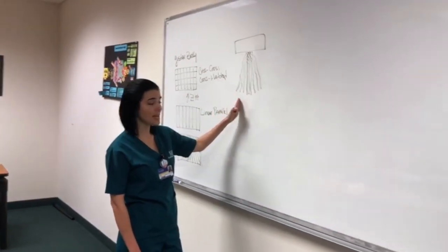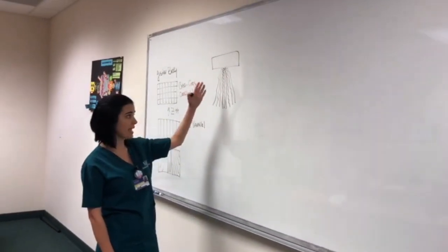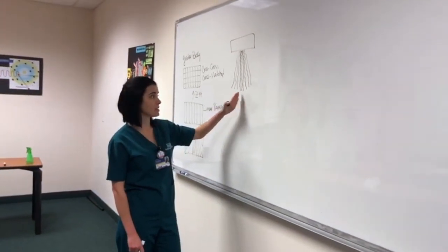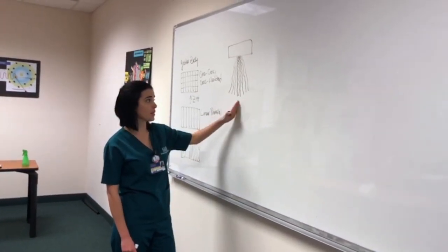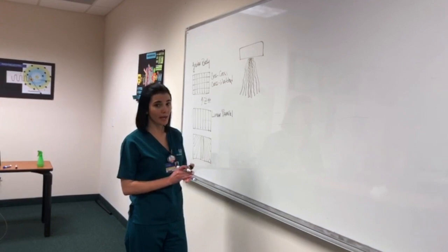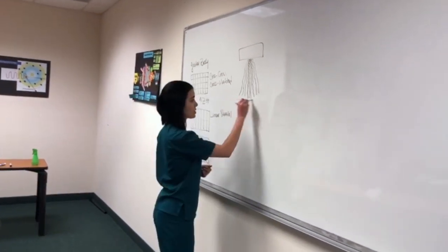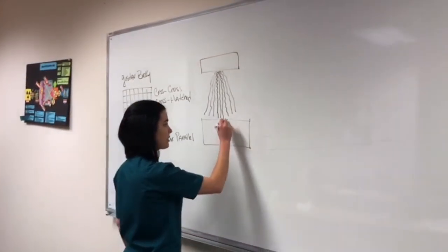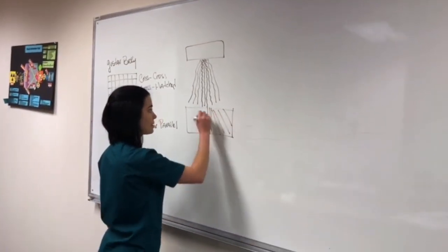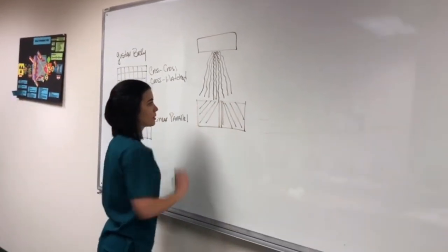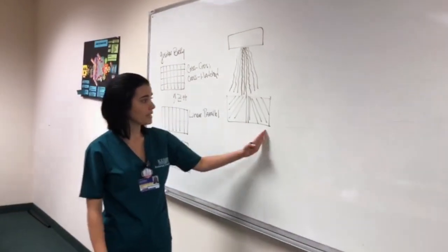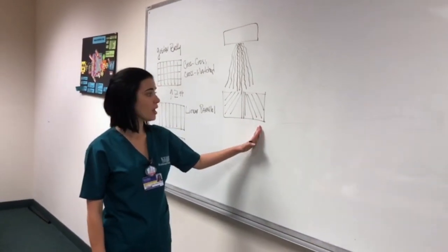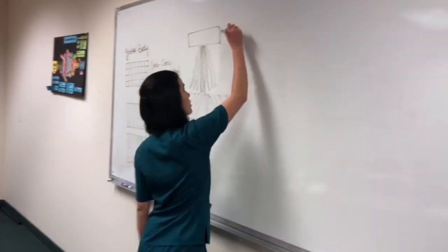Otherwise, the radiation information coming through the X-ray beam gets intersected by the lead strips, and that's a process we call grid error or grid cutoff. That's why we created this grid, with parallel lines and then slanted lead strips. So we need to understand the construction of the grid.